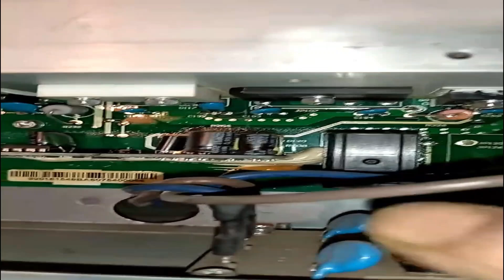There are two fans on the back side of this UPS. One is for cooling of this main board and the other is for cooling of this DC supply. You have to check that the two fans are working properly, meaning their RPM should be the same or constant. Then you have to check the input voltage. Power on the cable and then check whether voltage is coming or not. If voltage is coming properly, that is the input voltage.